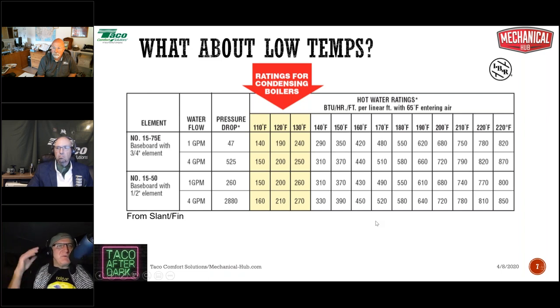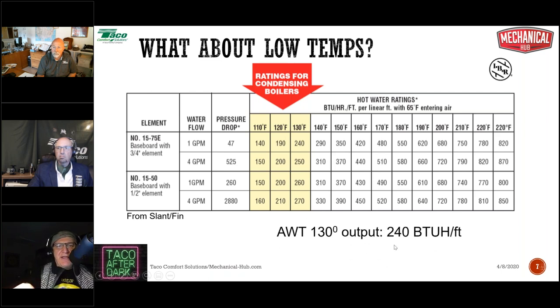So let's say we were doing this and we wanted to put in a modulating condensing boiler. All right, yeah, forget the existing baseboard. We're still sizing baseboard for this room. We want to put in a modulating condensing boiler, and we want that boiler to modulate as much as it possibly can and condense as much as it possibly can. So let's pick a number. Let's take a look at 130 degree average water temperature right there. So under design conditions, the water goes out at 140 and comes back at 120, giving us an average water temperature of 130 degrees. So that gives us 240 BTUs per foot.